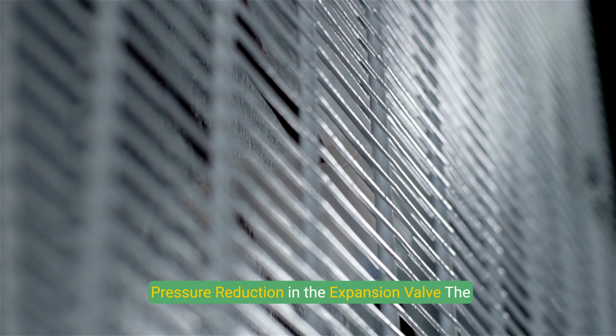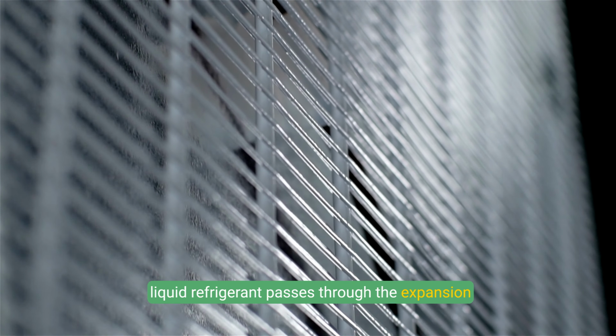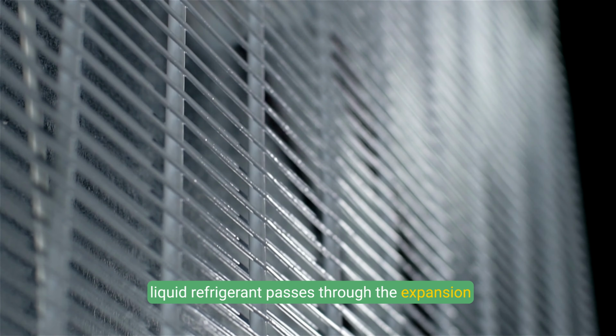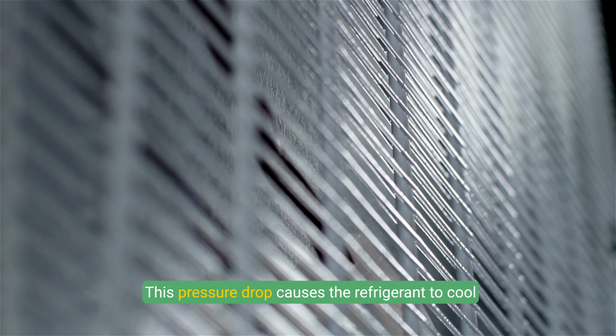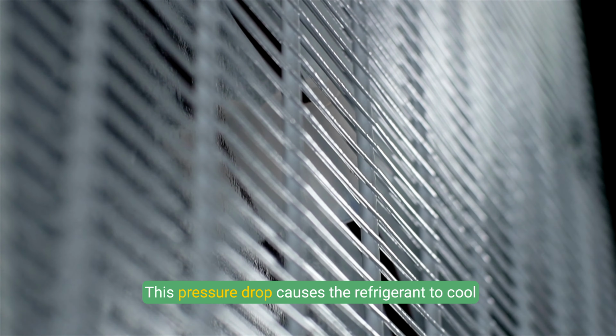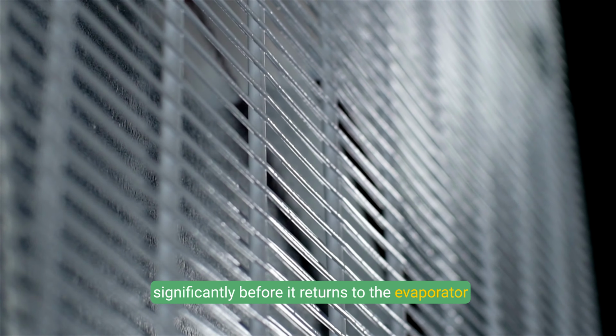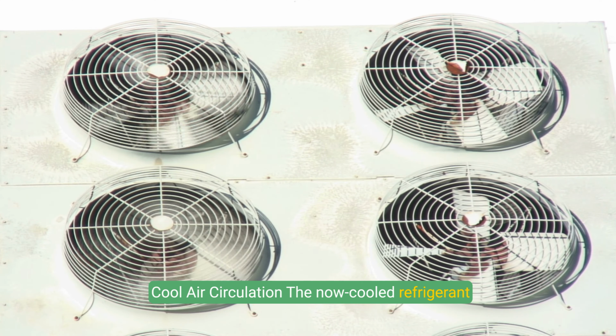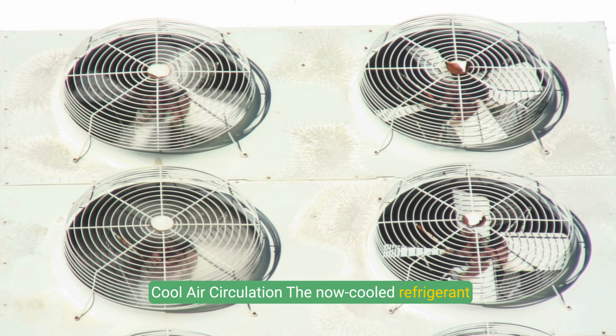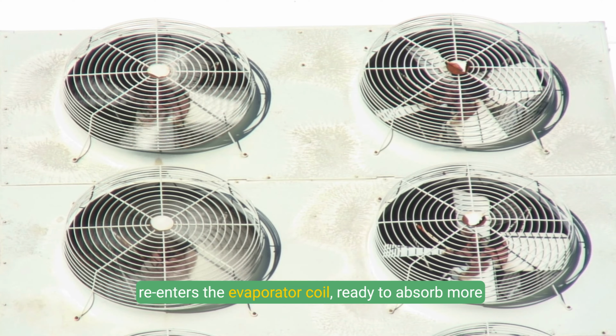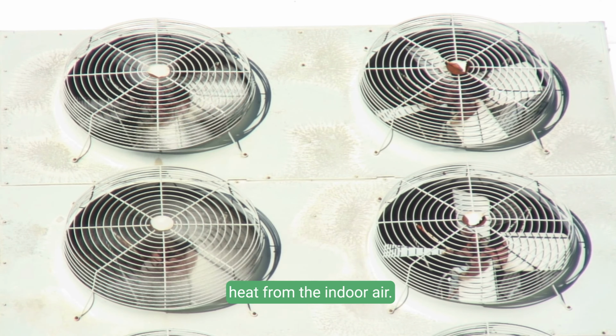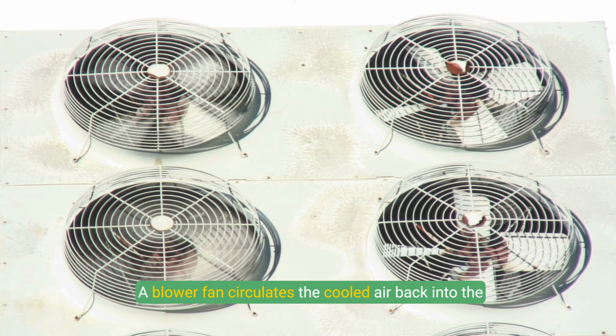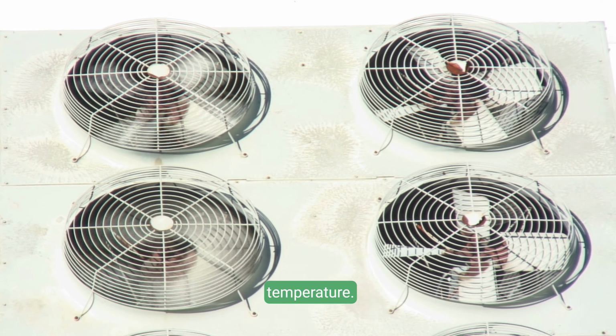5. Pressure reduction in the expansion valve. The liquid refrigerant passes through the expansion valve, which reduces its pressure. This pressure drop causes the refrigerant to cool significantly before it returns to the evaporator coil. 6. Cool air circulation. The now cooled refrigerant re-enters the evaporator coil, ready to absorb more heat from the indoor air. A blower fan circulates the cooled air back into the room via ducts or vents, lowering the indoor temperature.